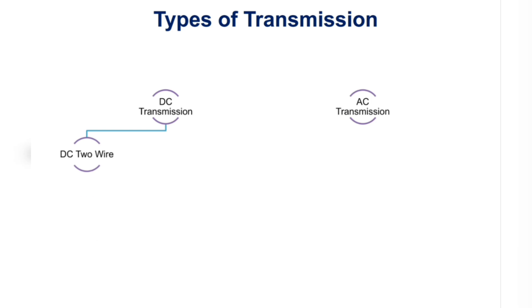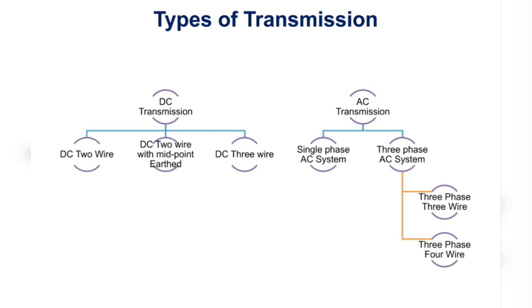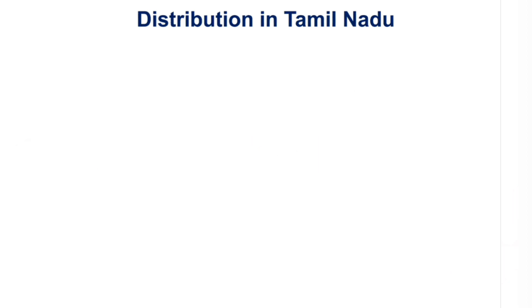When considering the various types of distribution systems, it may be a DC system or an AC system. In DC systems, it includes DC two-wire, DC two-wire with midpoint earth, and DC three-wire systems. In AC systems, it includes single-phase and three-phase systems. The three-phase system may be three-phase three-wire or three-phase four-wire. Typically, three-phase three-wire is used in primary distribution, while three-phase four-wire is used in secondary distribution.